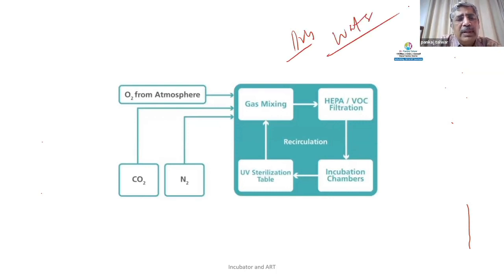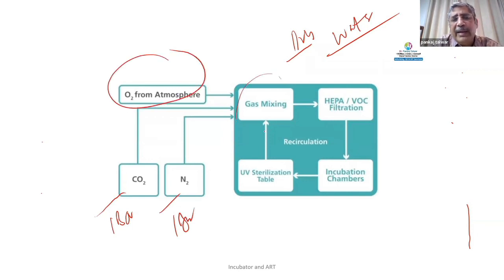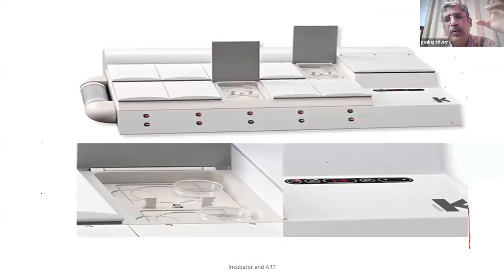So how do they work? They take carbon dioxide from a cylinder at 1 bar. They take N2 at 1 bar. Oxygen from the atmosphere. They have a gas mixer here. It will take the balance of gases from the room, filter them. It goes to the incubation chamber, and then it is UV sterilized and the gas is recirculated. That's the way these incubators work.